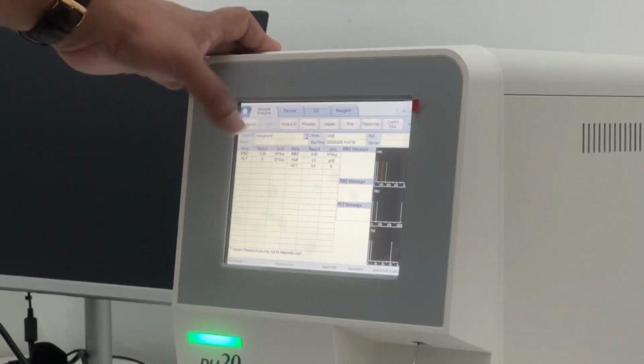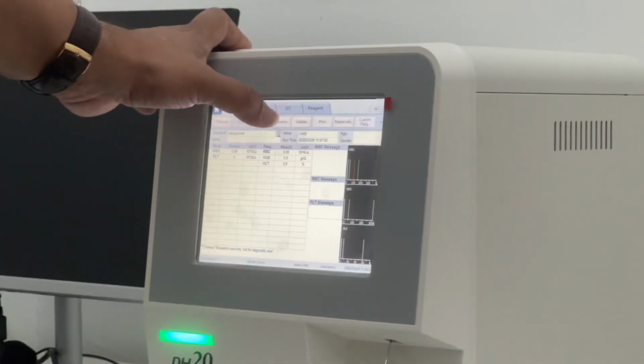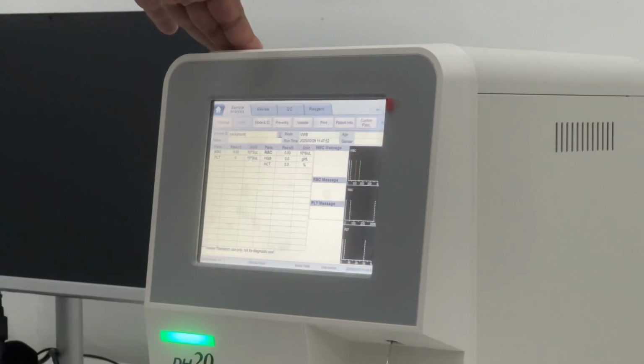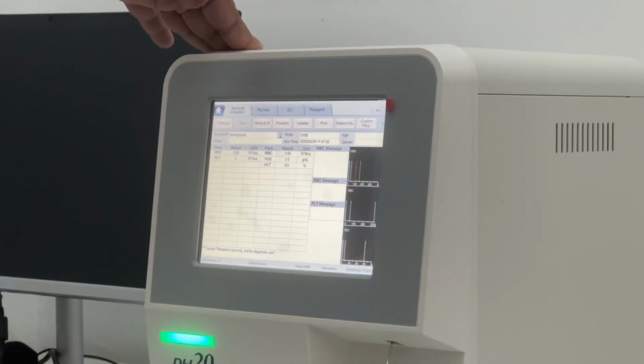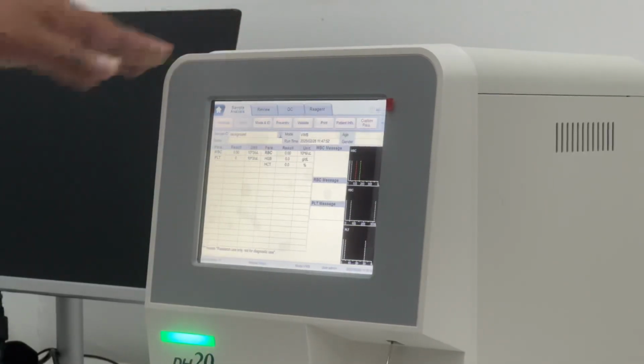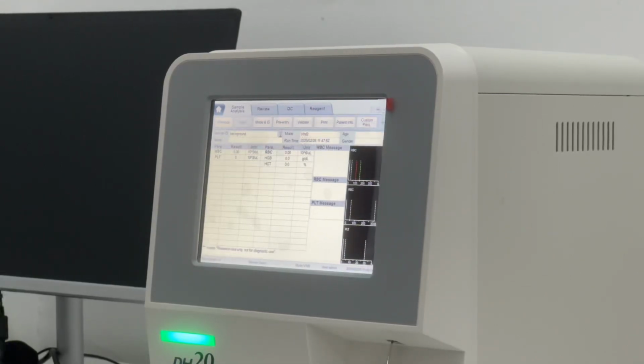This machine, before we run any samples, we need to check daily. We call it background checking. Why is background checking important? Any analyzers, we need to have quality control, QC. We need to do QC every day. But due to the cost, we cannot afford to spend the money on the QC. For that reason, the manufacturer came out with another idea, another technology. They put it as a default setting.